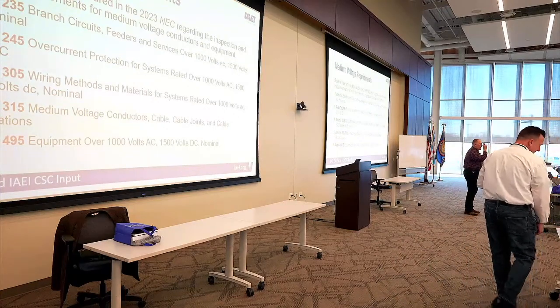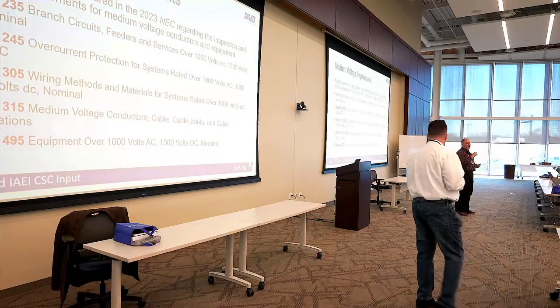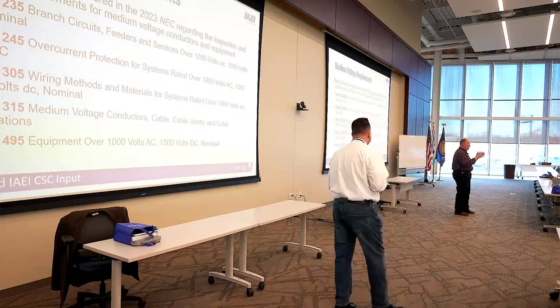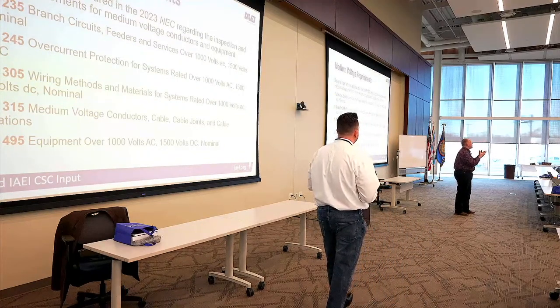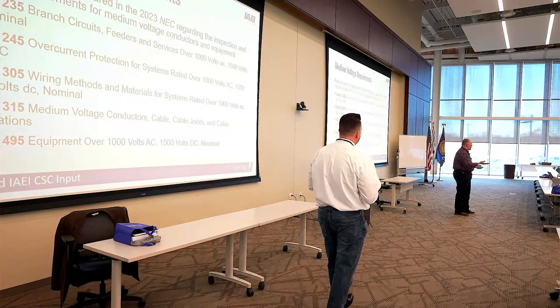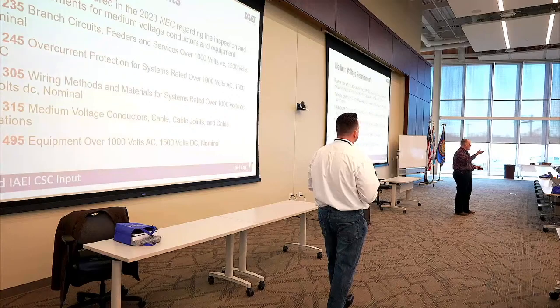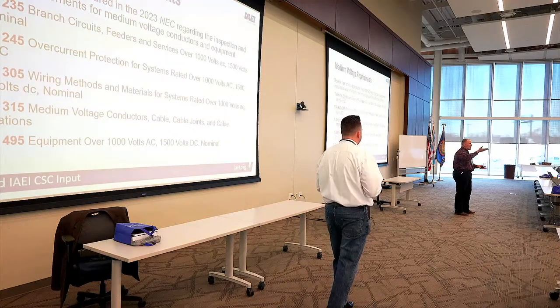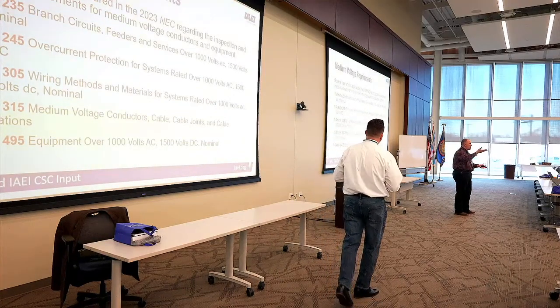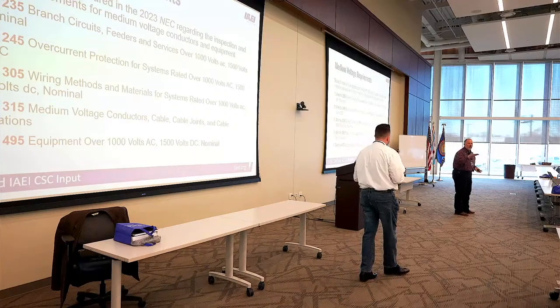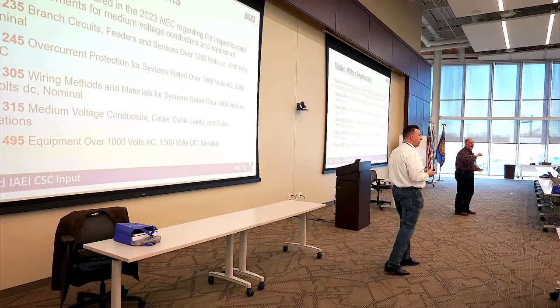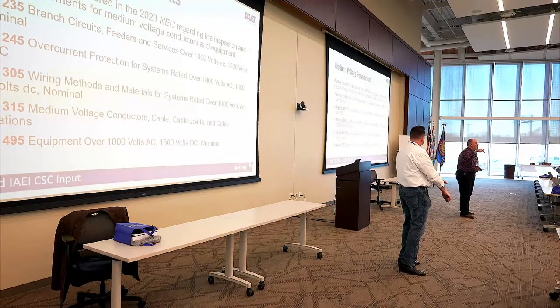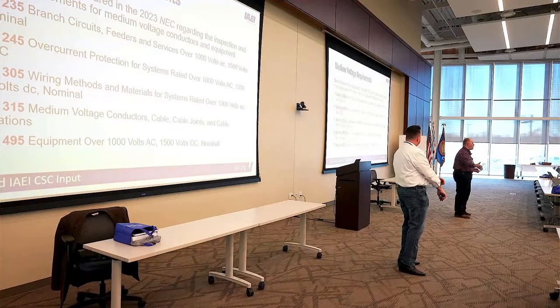So they took the transformer out of the inverters. When they take the transformer out, you lightened it up, took the iron out, took the loss out, but now to get the voltages you need, you had to pump it up. So they went up to 1,000 volts and said, I need 1,000 volts for medium voltage, because if I'm at 1,000 volts on my inverters since I took the transformers out, now I'm into medium voltage requirements, which adds a ton more issues to those applications.